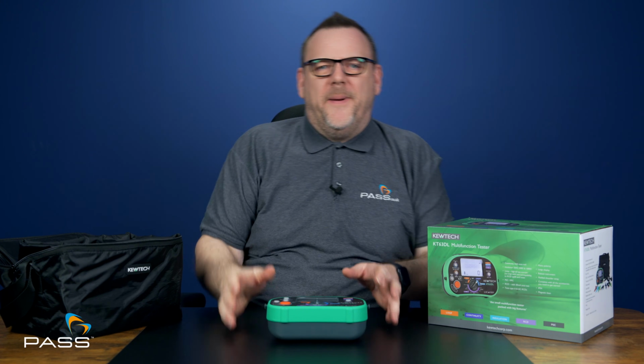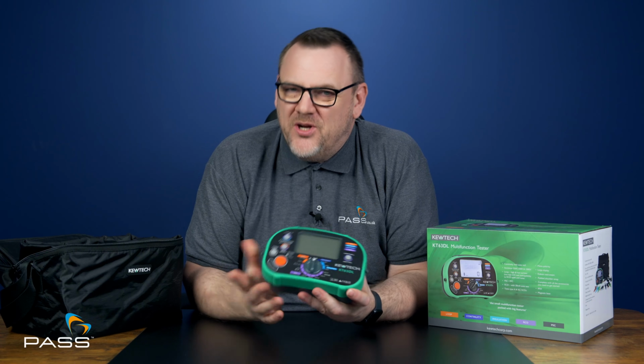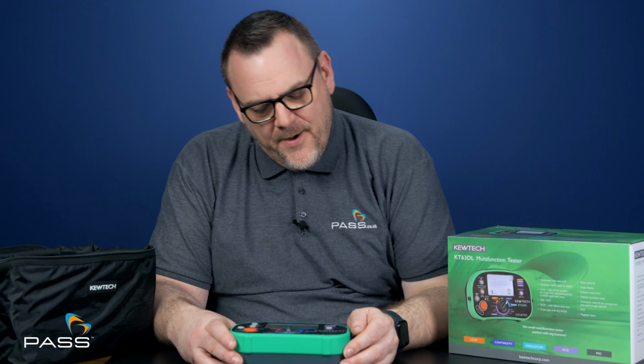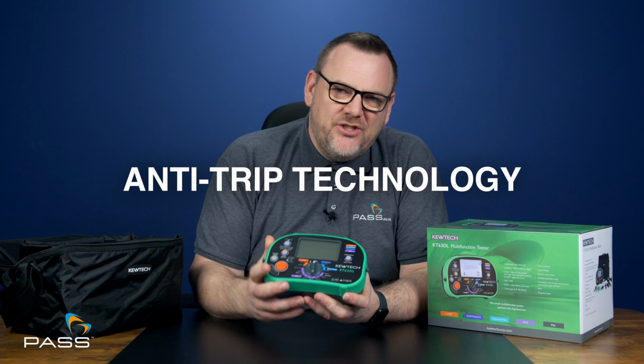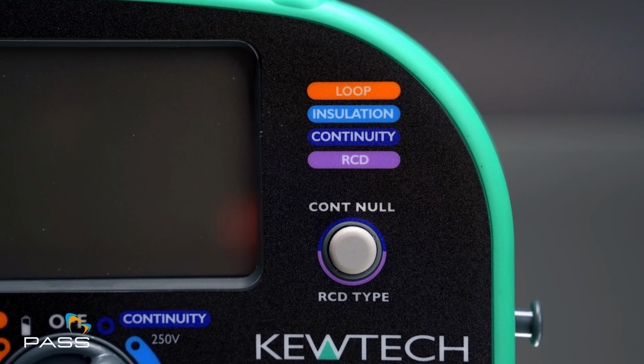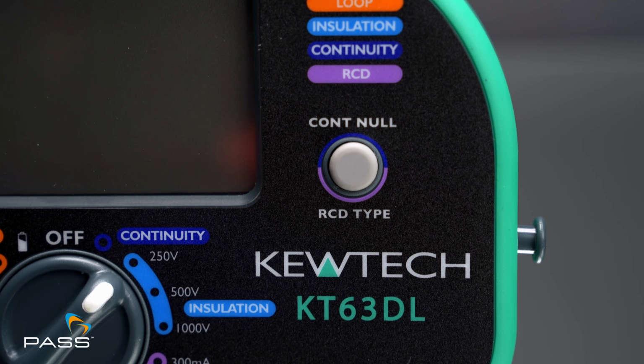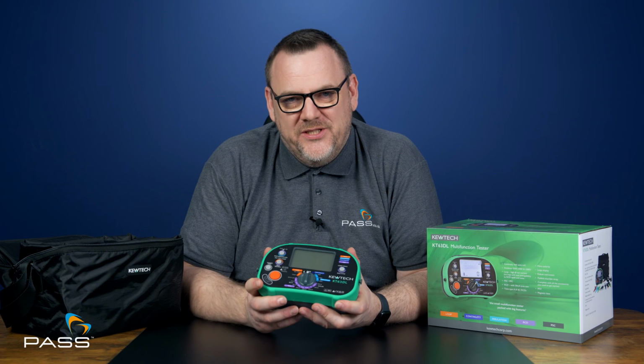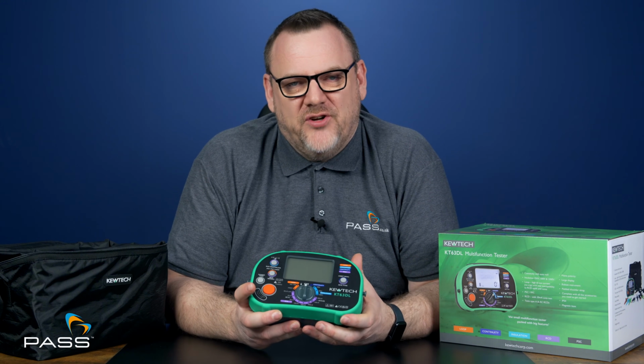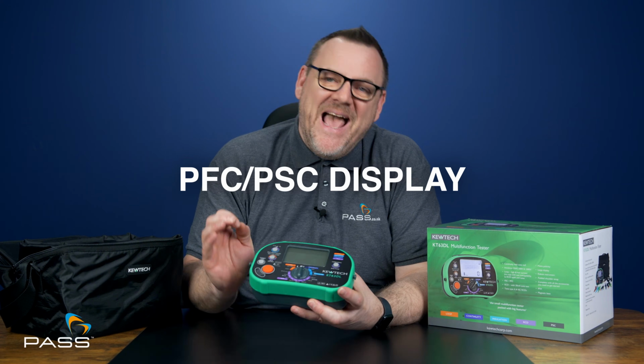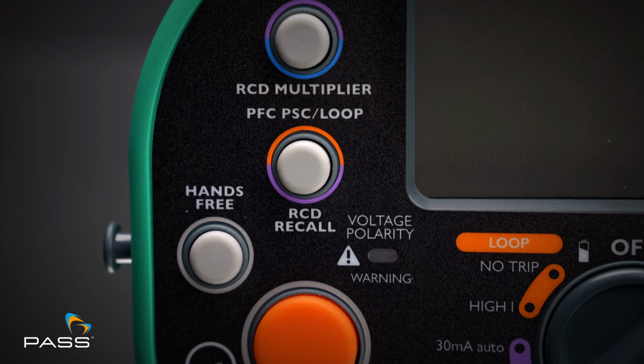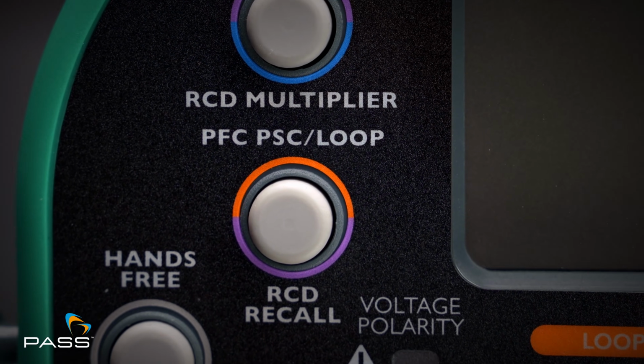So let's actually talk about what this tester can actually do, because it's not all about the looks. This thing is a powerhouse for domestic and light commercial work. Now, here's the highlight of the unit. Anti-trip technology, full no-trip loop testing on RCDs. Plus, it's got low susceptibility to noise interference. So, in translation, more accurate readings and less frustration. PFC and PSC display. This shows at the same time as your loop reading. So boom, you've got instant data.